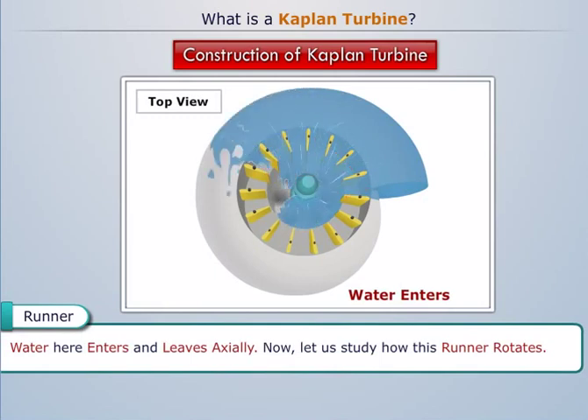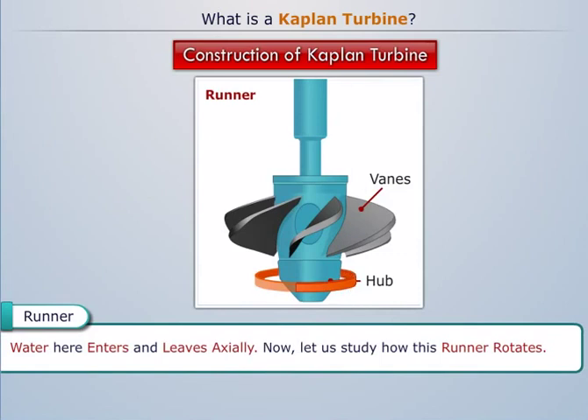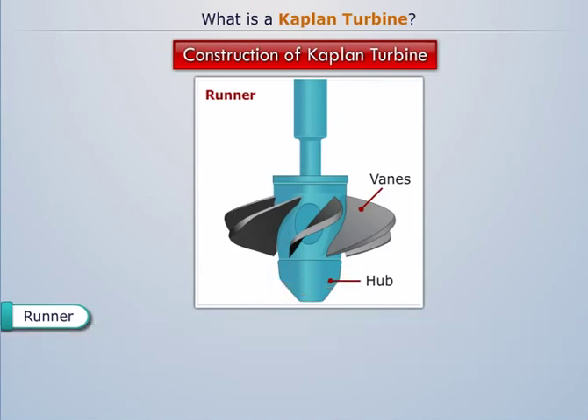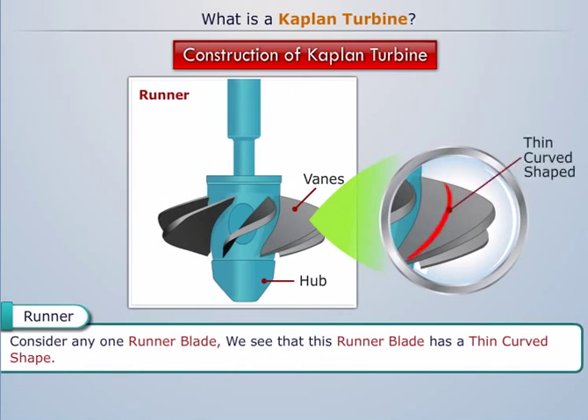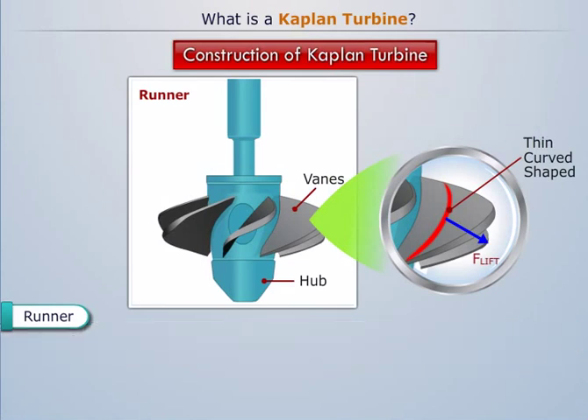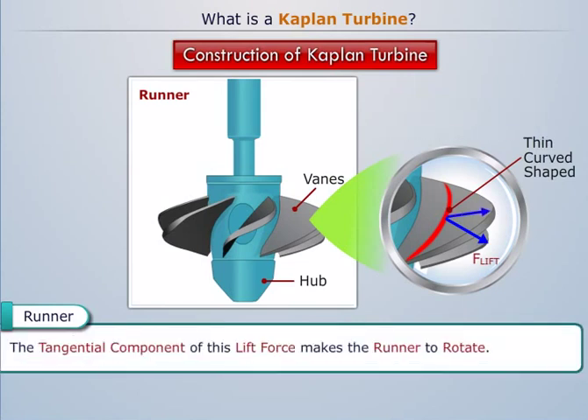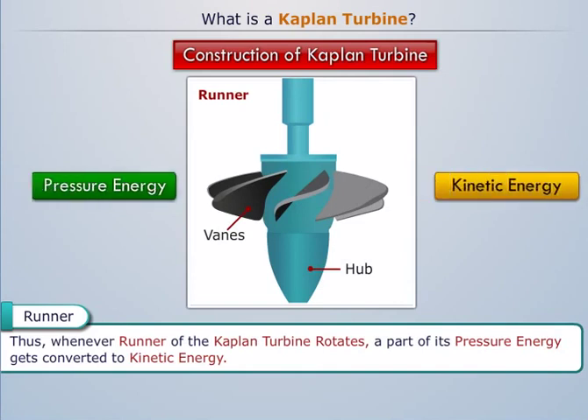Water enters and leaves axially. Now let's study how this runner rotates. Consider any one runner blade. This runner blade has a thin curved shape. As a result, whenever water flows through the hub, the water induces a lift force due to the airfoil effect. The tangential component of this lift force makes the runner rotate. Thus, whenever the runner of the Kaplan turbine rotates, a part of its pressure energy gets converted to kinetic energy.